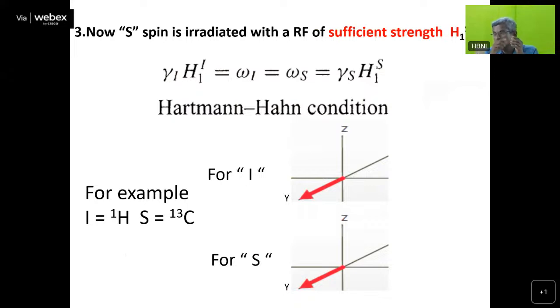Through one coil, sir. In solid state NMR, only one coil is there. Through a single coil only, with different time scales, we can apply both these pulses. And these are pulsed signals, not continuous. And one more thing, sir: the carrier frequency. Because a pulse as such we cannot apply, we take a pulse and mix it with the carrier frequency. So carrier modulated pulses we are applying.